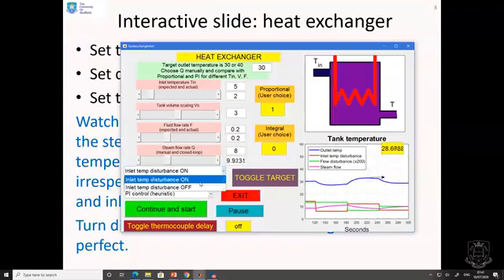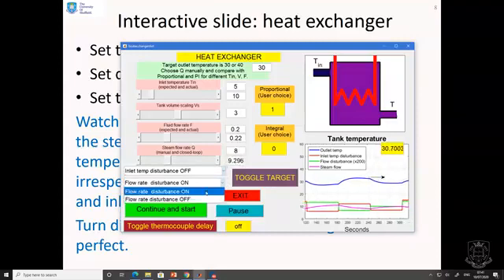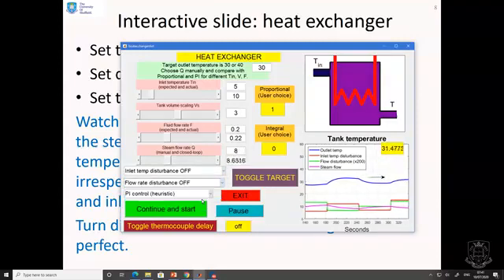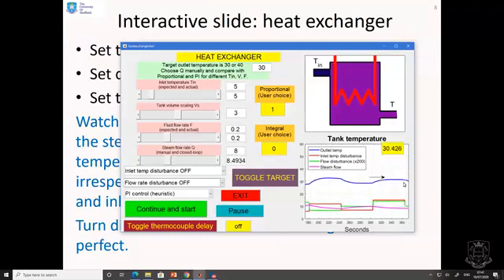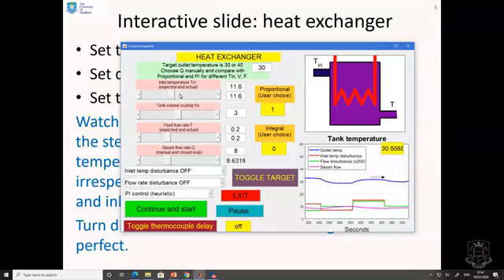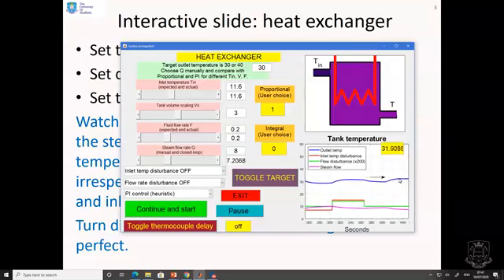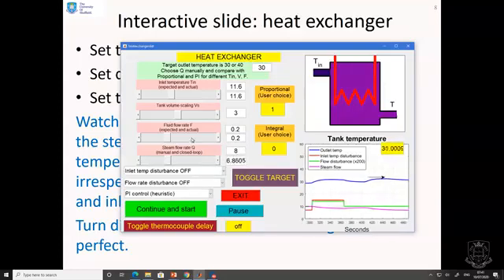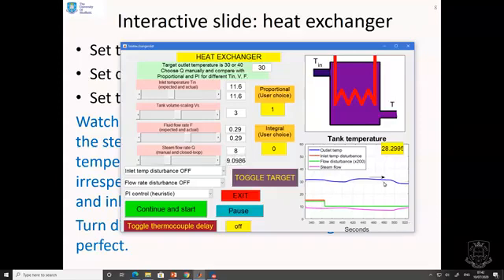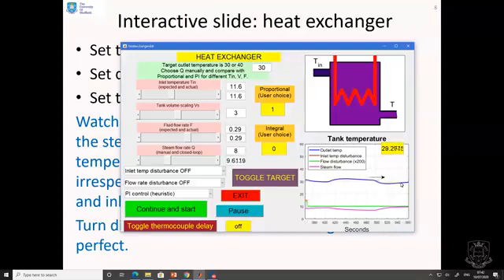If we want to show this more slowly, we can put those disturbances off and make manual changes. We'll give it time to settle - the PI compensator will bring it back to 30. Now the temperature has come back to 30. What I can do is artificially change the inlet temperature - that's quite a big change, 6 degrees. Notice the PI is going to bring the temperature back about as fast as you reasonably could, given the size of this tank. We could also change the fluid flow rate. Again, you see how the steam flow has been changed automatically by the PI and it's bringing the temperature back - about as quick as a human could do it, if not maybe quicker.